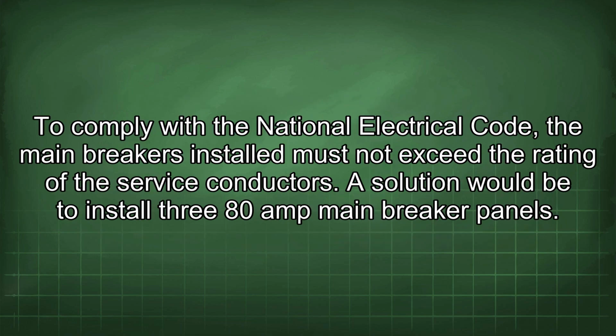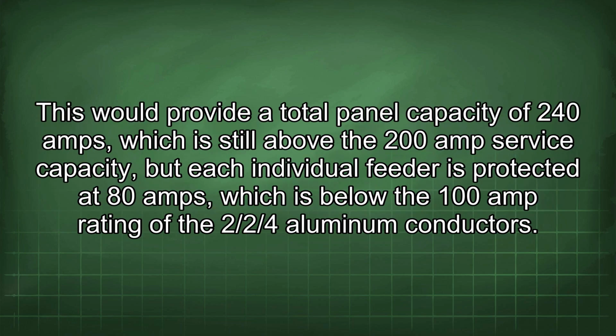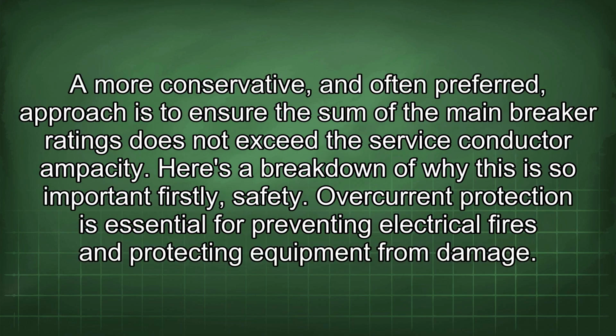To comply with the National Electrical Code, the main breakers installed must not exceed the rating of the service conductors. A solution would be to install 3 80 amp main breaker panels. This would provide a total panel capacity of 240 amps, which is still above the 200 amp service capacity, but each individual feeder is protected at 80 amps, which is below the 100 amp rating of the 2/2/4 aluminum conductors. A more conservative, and often preferred, approach is to ensure the sum of the main breaker ratings does not exceed the service conductor ampacity. Here's a breakdown of why this is so important.